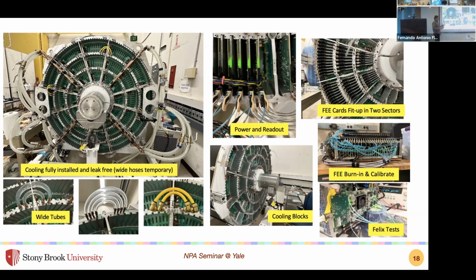And all these slots are then connected with a gap pad, which is a highly thermal conductor material. So once the plate touches the wedge, it's cooled. The connection is awesome there. And these water lines are not running at normal pressure, they are running at sub-pressure. So less than the atmospheric pressure. So if you pull this tube out, nothing will happen. Water will go in. So even if you have a disconnect or something bad happens, it will go in, not out. So there is almost a very small chance of leakage or any such thing. So that all works really well.